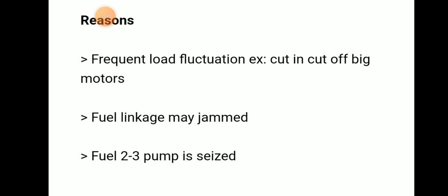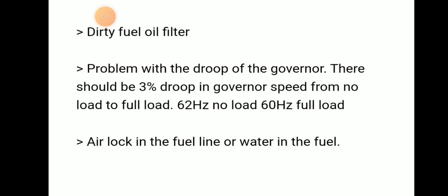To recap: frequent load fluctuations, fuel linkage may be jammed, 2 or 3 fuel pumps seized, dirty fuel oil filter, problem with the governor droop — it should be 3% governor speed from no load to full load — and air lock in the fuel line or water in fuel.